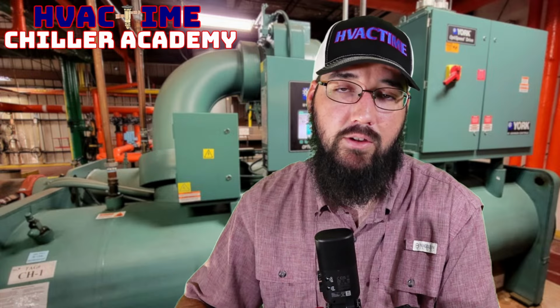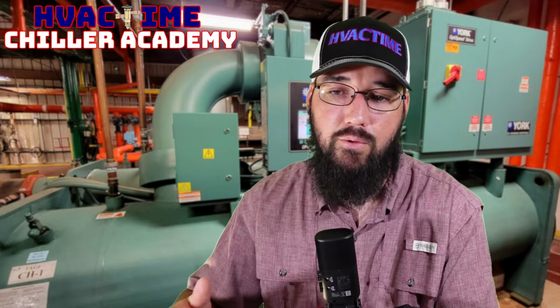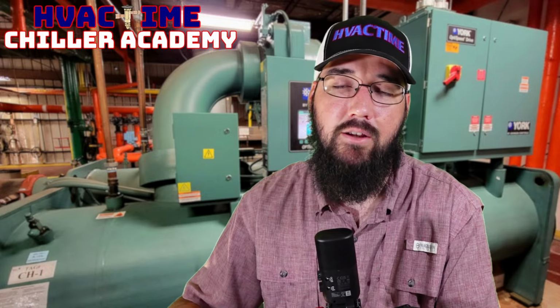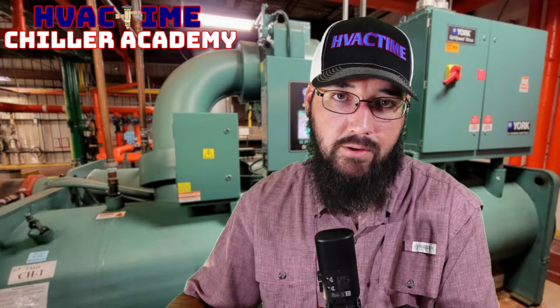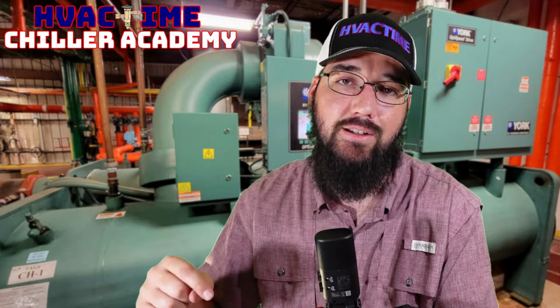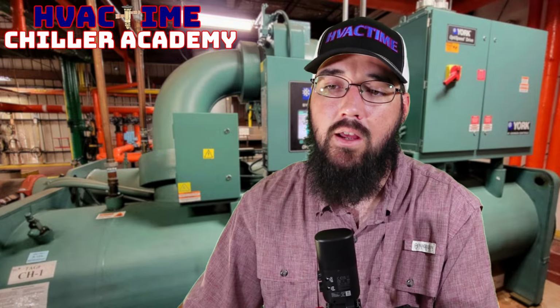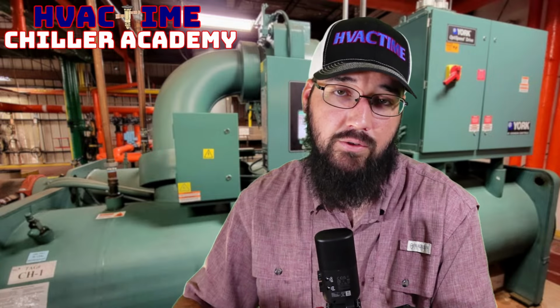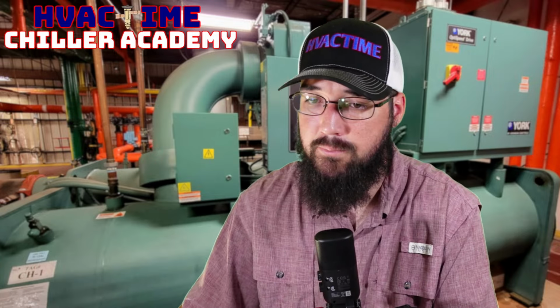Be careful in the event that you have a braze plate economizer or just an economizer in general. In those systems, I always take my subcooling before the economizer, not after. You want to take the subcooling actually leaving the condenser coils. And that is what most of the literature will be. If they give you a subcooling value, that's what that value is representing. This is pre-economizer subcooling, not post.